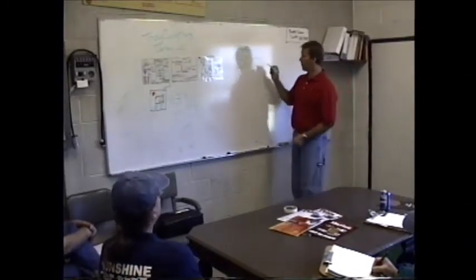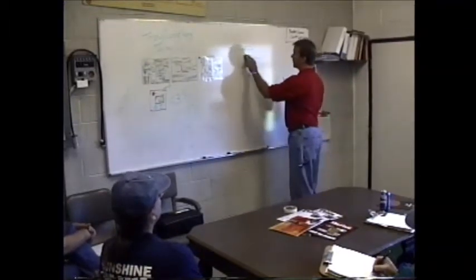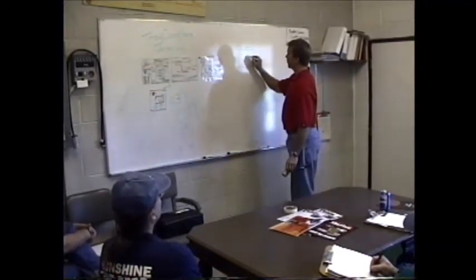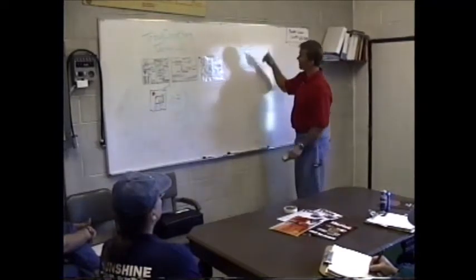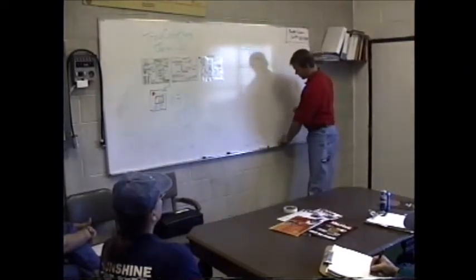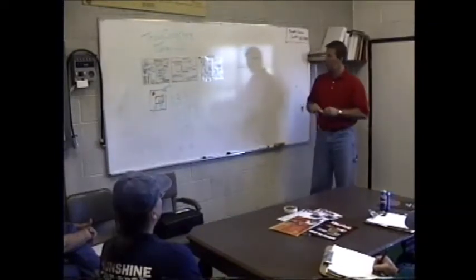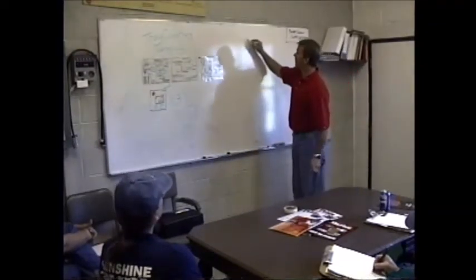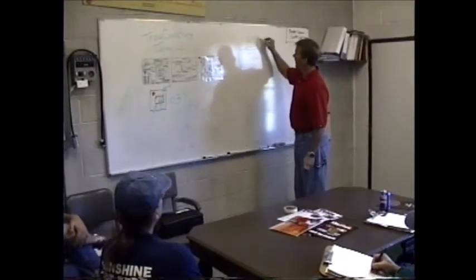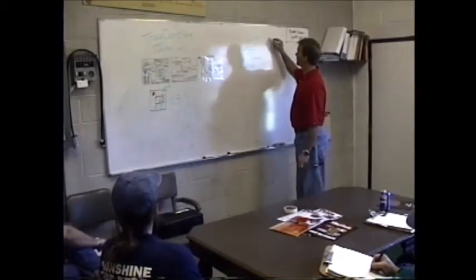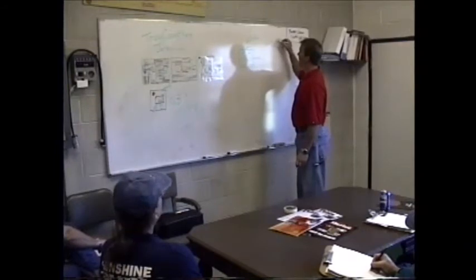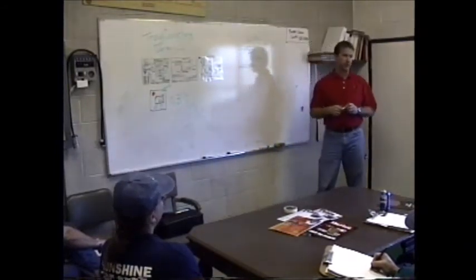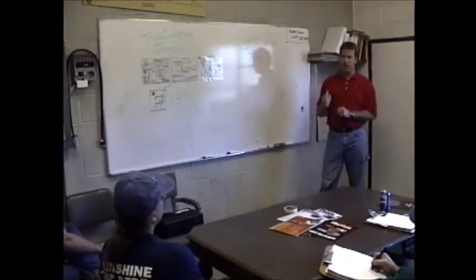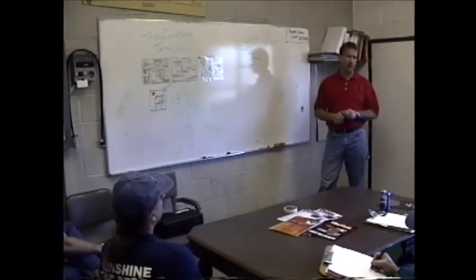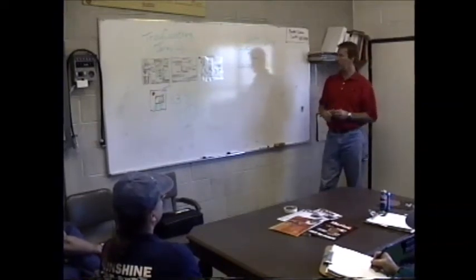And where we're gonna have those set right now is basically about 60 CFM, which is darn near one half of its full open position, roughly about 60 CFM. And that's about perfect for mixing with that 60 GPM of water for a really nice firefighting stream, a really high velocity stream. Hang on and point it at the fire and you'll be amazed how fast it goes out. But that's about where we set it.